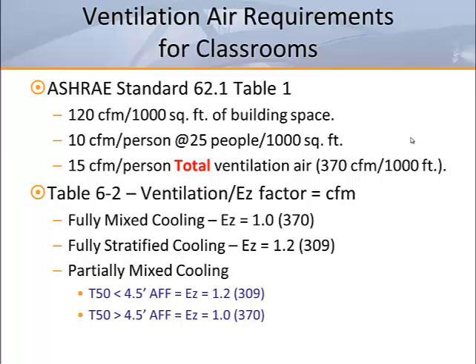Table 6-2 identifies the adjustment factor for getting the ventilation air into the breathing zone of the space. Based on a fully mixed cooling with an EZ of 1.0, the ventilation air requirement is still 370 CFM. Displacement ventilation gets extra credit. So, when 370 CFM is divided by EZ 1.2, the result is 309 CFM for displacement ventilation.